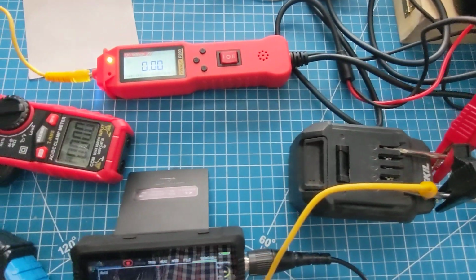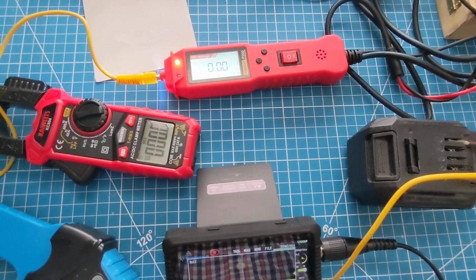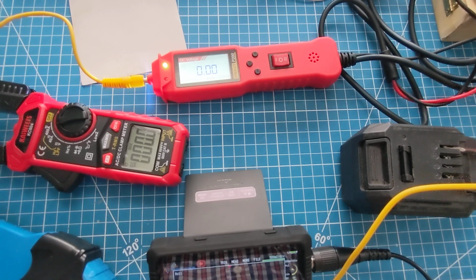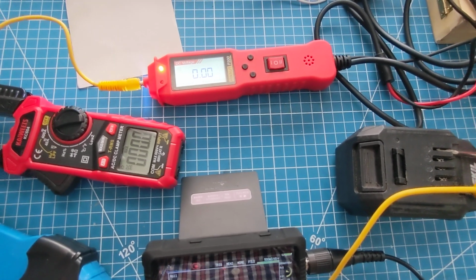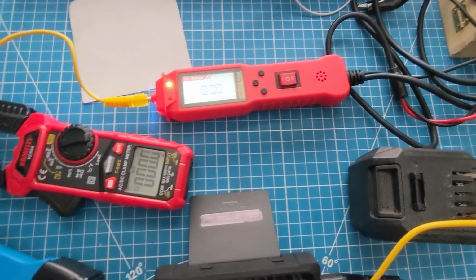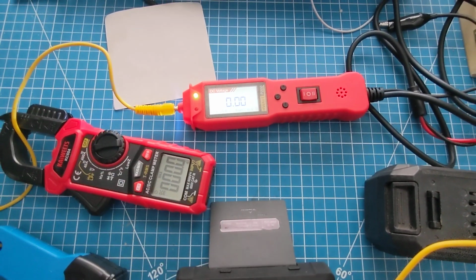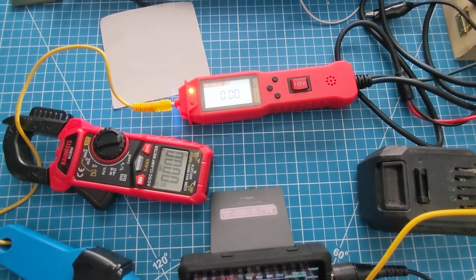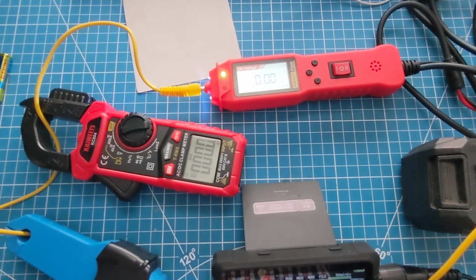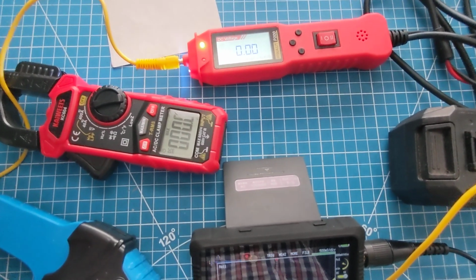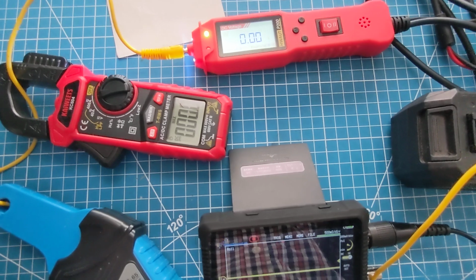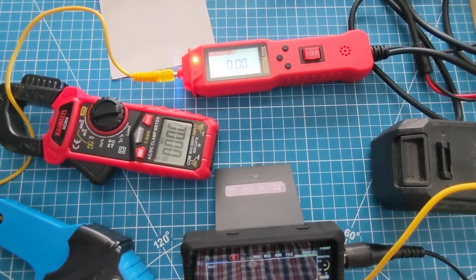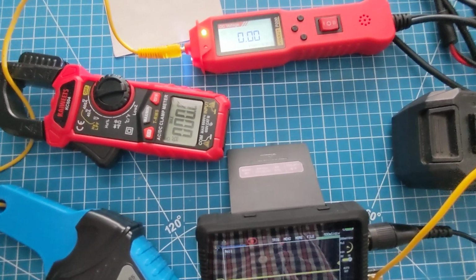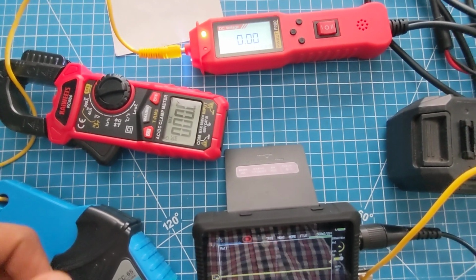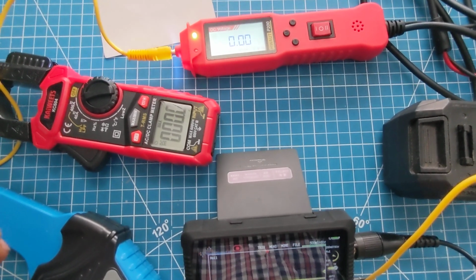Ideally, it's supposed to have proper short circuit protection, a breaker circuit that instantly trips to prevent damage to components under test. In this case, we'll see it takes about a second, sometimes slightly more, and peaks at about 50-something amps, which can be dangerous and can damage sensitive, even not-so-sensitive, components given that current and the time before the breaker trips.